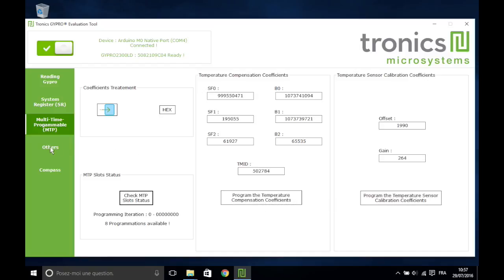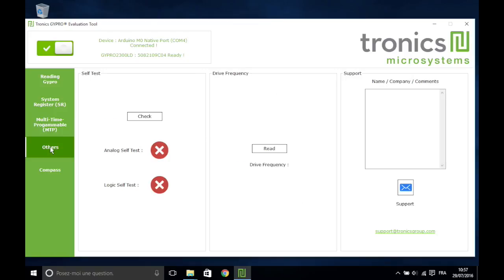Now move to the tab called Others. You can check the status of the two self-tests and measure the drive frequency of the sensor.